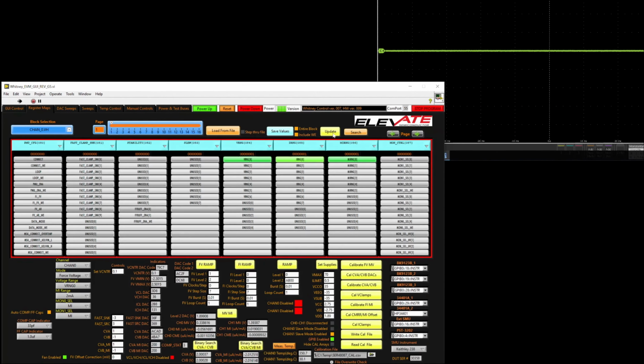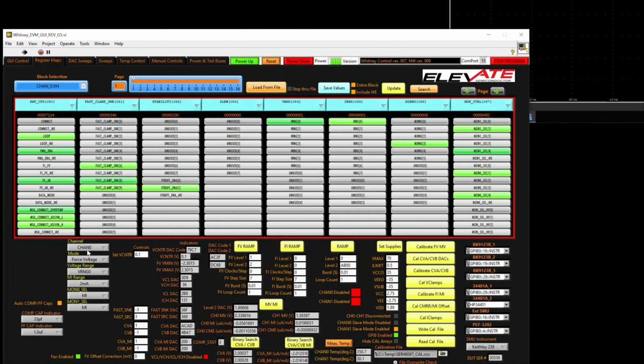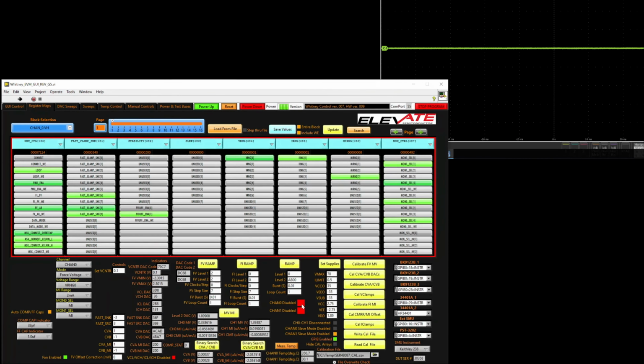In the bottom left of the GUI, all of these settings can be confirmed. We will select channel 0, make the mode FV, change the range to VRange 0, and set the current range to 2 milliamps. In order to confirm that FV is working correctly, I will program the FV level 1 to 2 volts and the FV level 2 to 2 volts. This will program the voltage level at the output to be 2 volts. After enabling the channel by clicking on the red box next to the Chan 0 Enable Disable, it will turn green and the output can be seen jumping to 2 volts.